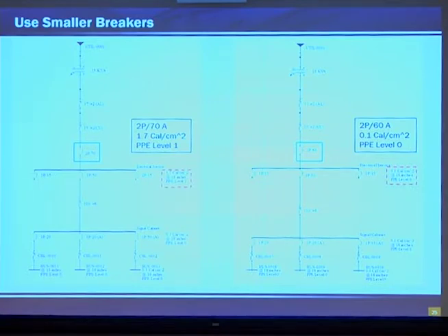That's just changing the descriptive code. Simple. Same thing happened with illumination, going from a 2-pole 70 breaker to a 2-pole 60. We keep designing these systems for the future, and especially for illumination. Oh, let's put a spare breaker in there. We're going to come back and add a couple other legs on this illumination. Or we're designing for HPS lighting when we're moving to the LED world, or incandescent lighting when we have LED circuits.